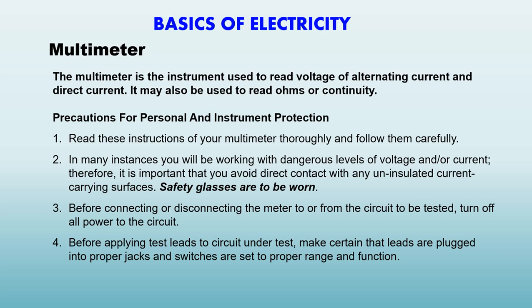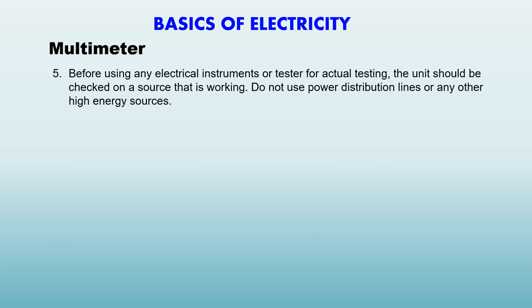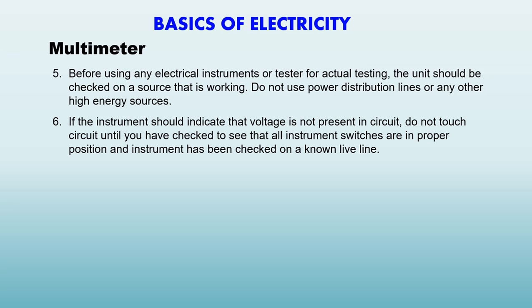Before applying test leads to circuit under test, make certain that leads are plugged in to the proper jacks and switches are set to the proper range and function. Before using any electrical instruments or tester for actual testing, the unit should be checked on a source that is working. Do not use power distribution lines or any other high energy sources. If the instrument should indicate that voltage is not present in the circuit, do not touch the circuit until you have checked to see that all instrument switches are in proper position and the instrument has been checked on a known live wire.